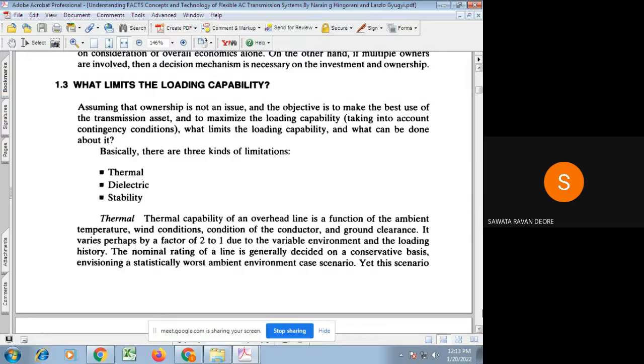So because of that, the given transmission line may have two or three thermal ratings. According to that ambient condition, that line may be loaded with a thermal rating of 1000 megawatt or maybe 800 megawatt or 900 megawatt, if the atmospheric condition is varying accordingly. So in view of actual loading of the transmission line, some real-time computers are used to estimate the thermal rating of the line, and according to that, the line can be loaded up to that only, in order to avoid further inconveniences or further transients, we can say.